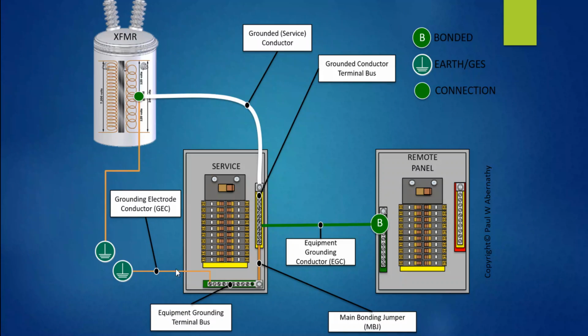Now, this is the one where I show you that when you do this setup, the code does permit you to bring the grounding electrode conductor to this terminal bus when this is of the wire type, okay? And that's the one we're sticking with, because I happen to work for a wire and cable manufacturer, and we're going to go with that.